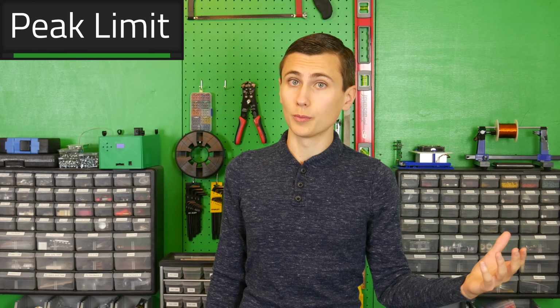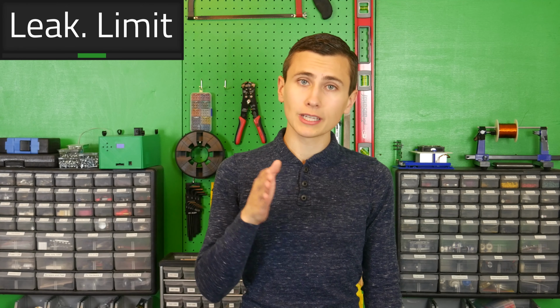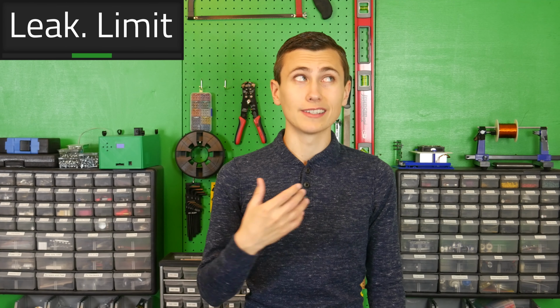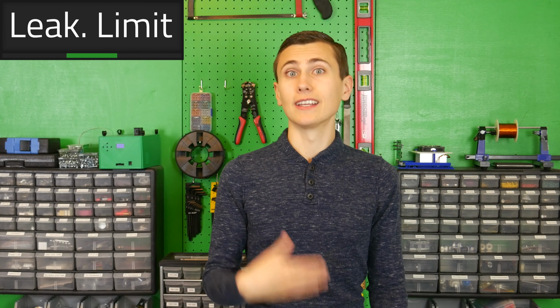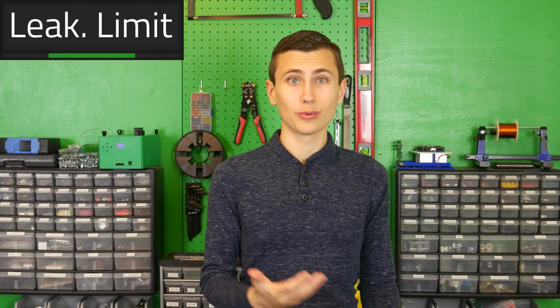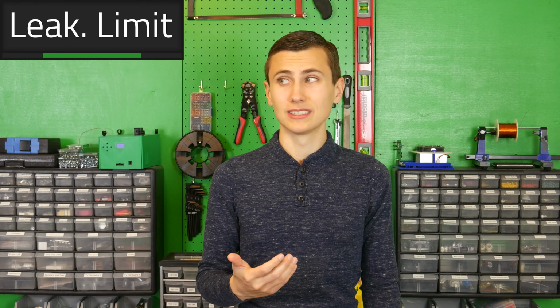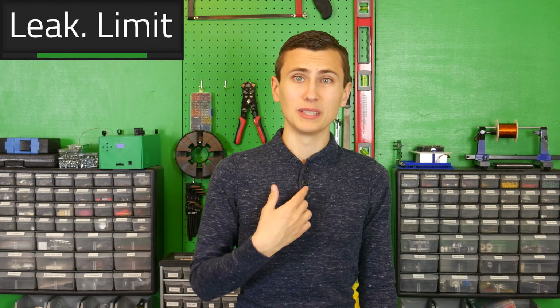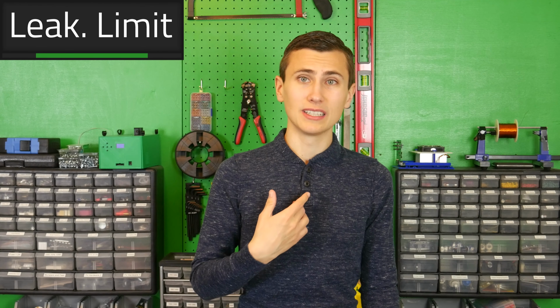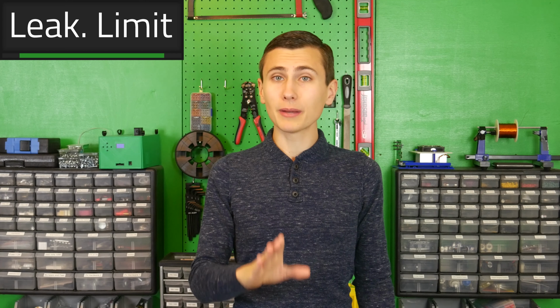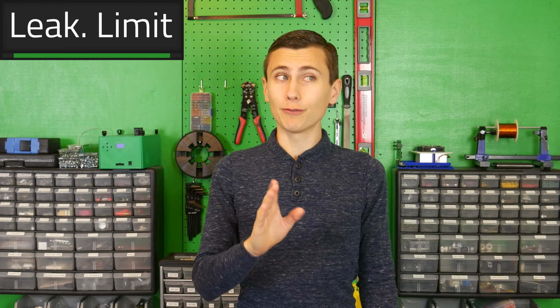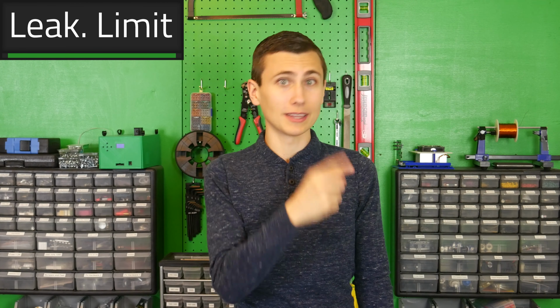The leakage current limit is also very important. Like we said before, if there's current coming out of one half of the inverter and it's never coming back, it needs to be going somewhere. More likely than not, this current is leaking back to earth ground through, well, probably you, me, our dog chewing through the mains cord. I have no idea where the current's going, but it's probably best to shut down and figure out where that current's going later.